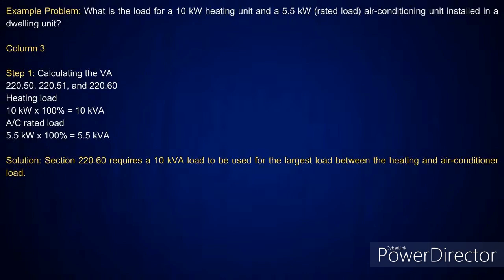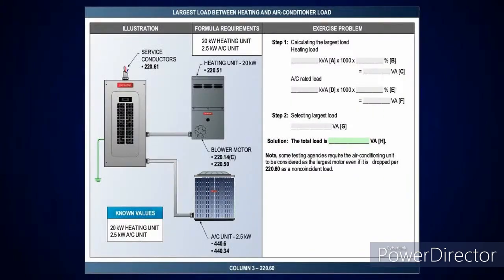All right. I've got a 10 kW heating unit and a 5.5 kW air conditioning unit load. Now, when you look at this and you pick up 220.60, it says if it is unlikely that 2 or more non-coincident loads will be used simultaneously, using only the largest loads that will be used at one time for calculating the total load for the feeder or service shall be permitted. So these are not going to be operating at the same time. They're non-coincident. So whichever is the largest between the two, we're going to take and we're going to drop a load. So here I'm going to drop the AC load. It's the smallest load. It's 5.5 kVA, and the heating load is 10,000 VA. So I would take this and I'd just put 10,000 VA on to my steps here when we get to the full calculations. All right.